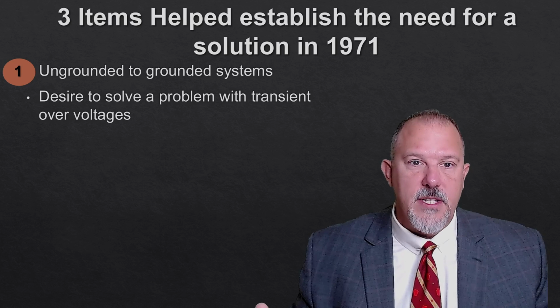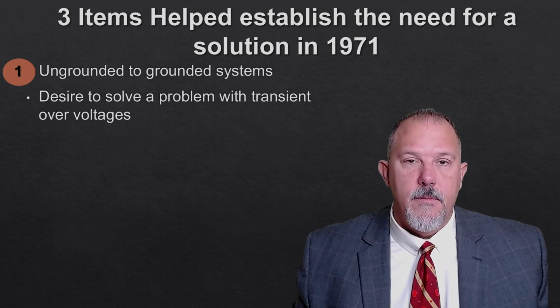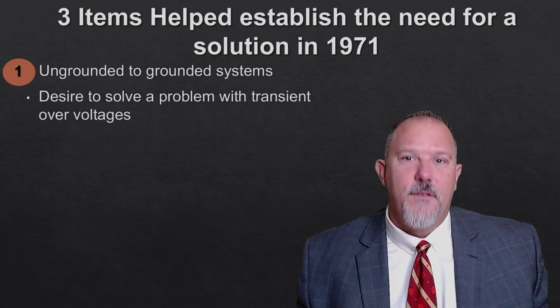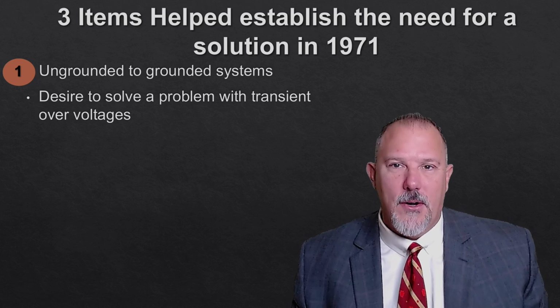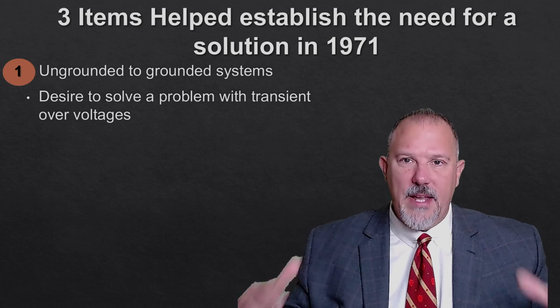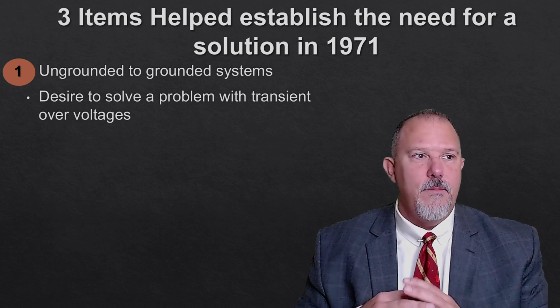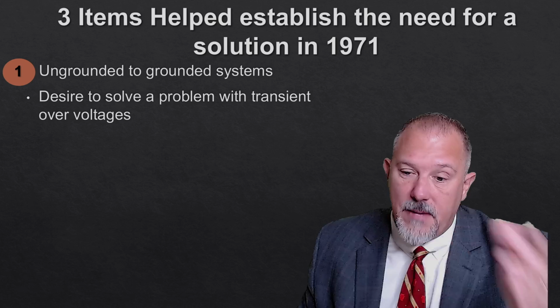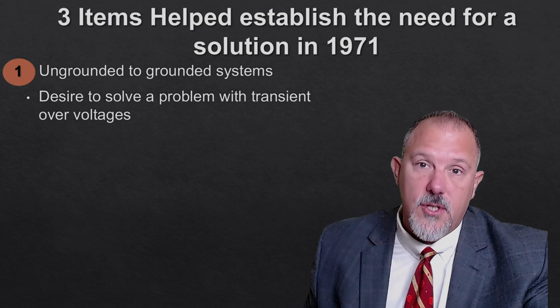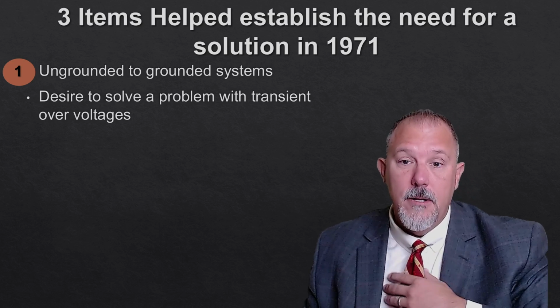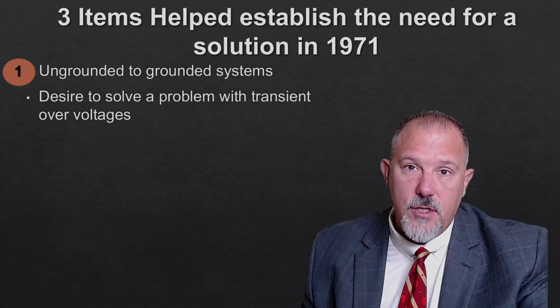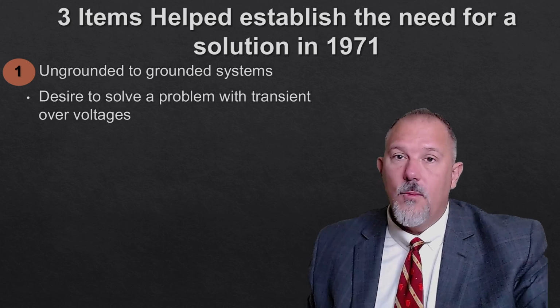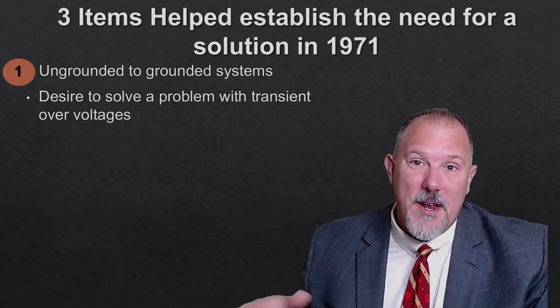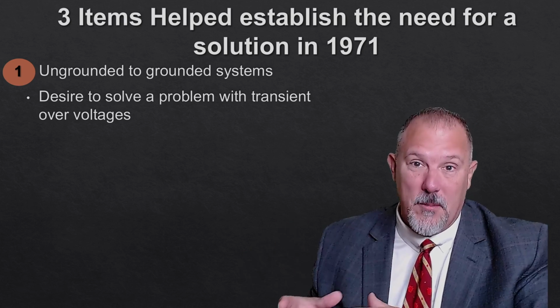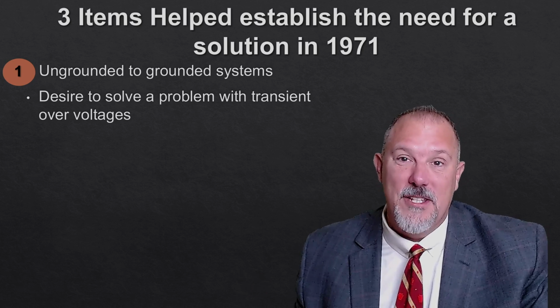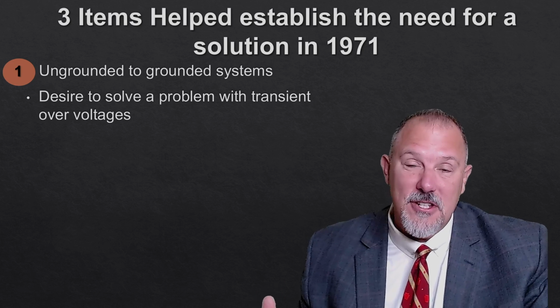Now, someone probably somewhere said, hey, during a fault condition, we can operate pretty doggone good, and it makes the system more reliable. So they started grounding. In fact, the first coordination and short circuit study that I ever did in my career was for a Union Carbide plant in West Virginia. It was a delta system. I called it the spider on the one-line diagram, but it was a zigzag transformer, because I didn't know what a zigzag transformer was back in the day. This was my first exposure to it.